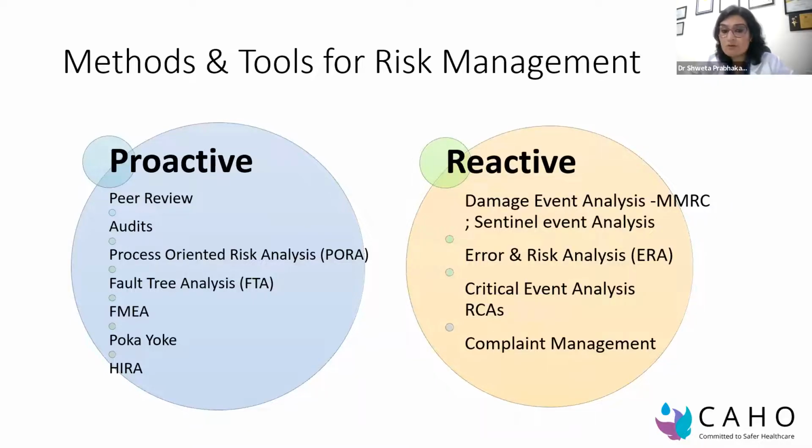Then you would do an RCA, you would identify what has happened. When you do a why-why analysis, why it happened, that would lead you to: yes, that was the reason there was a short circuit, because there was an infusion running through an IV line above the infusion pump, and it was leaking, and it caused a short circuit. So this is a reactive approach.